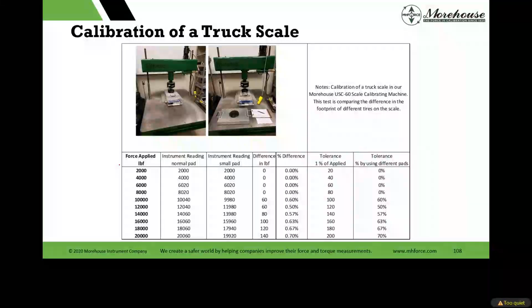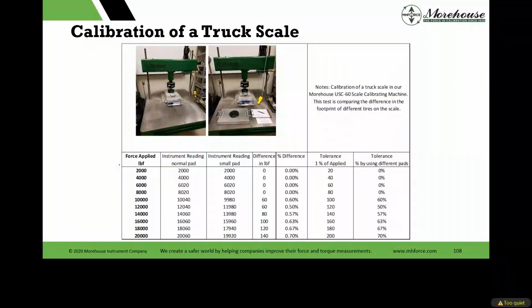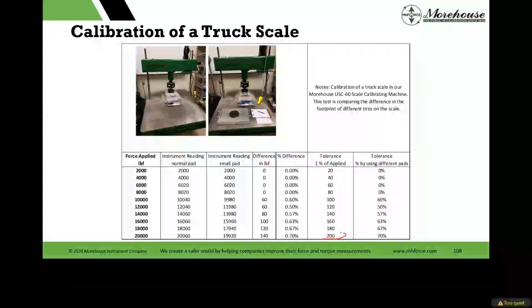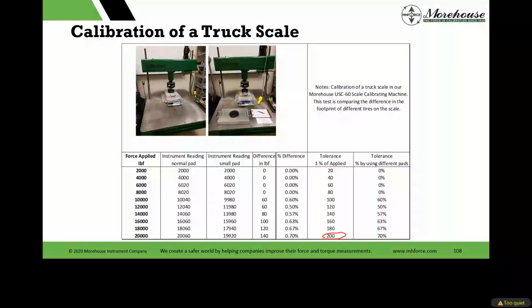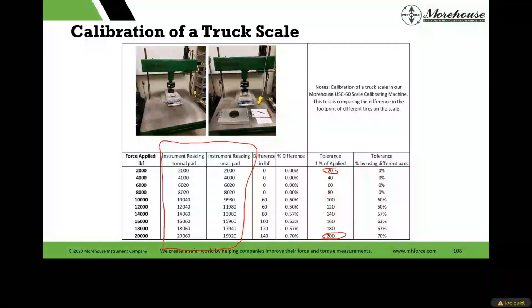So knowing that the specification on this scale is plus or minus 200 pounds. Well, it's actually 1% of applied, so it varies from 2,000 to 20,000, from 20 pounds to 200 pounds. And what we observed with the different footprints here is a difference in readings. Those readings were still within the tolerance, though what you have to worry about is, when we have a tolerance of plus or minus 200, what if I was closer to one of those tolerances? Would I call it out when it's actually in by using a different rubber footprint or not?